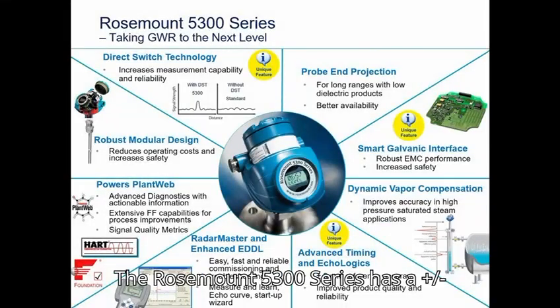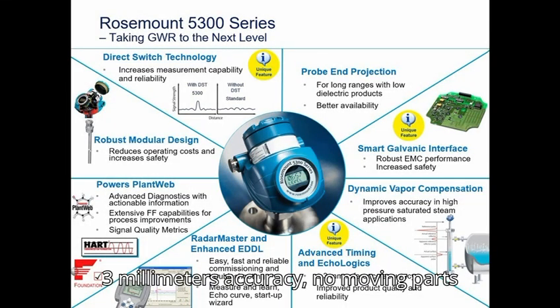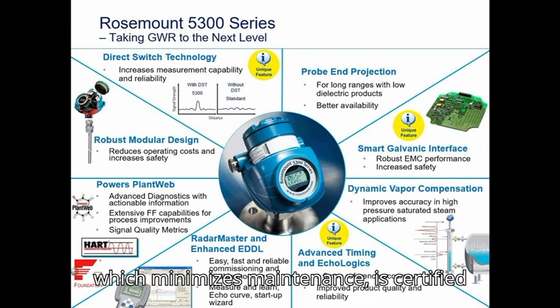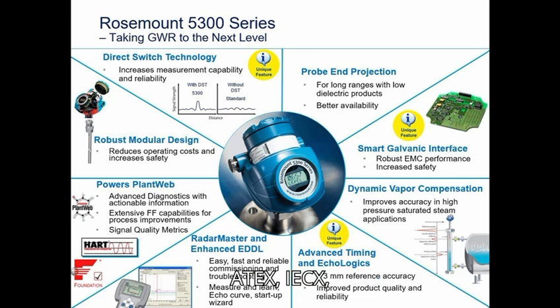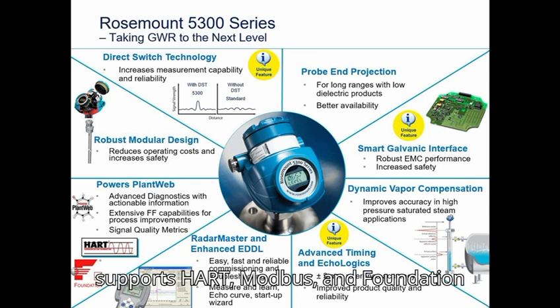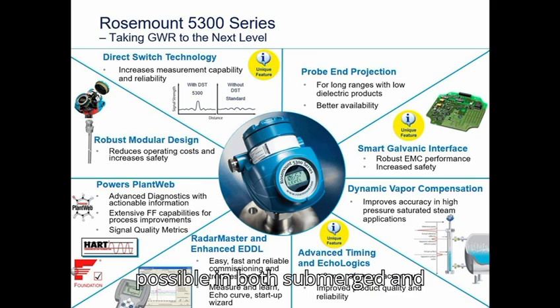The Rosemount 5300 series has a plus or minus 3 mm accuracy, has no moving parts, which minimizes maintenance, and is certified ATEX, IECEx, SIL2/SIL3 for hazardous areas. It supports HART, Modbus, and Foundation Fieldbus. Its interface measurement is possible in both submerged and non-submerged applications.